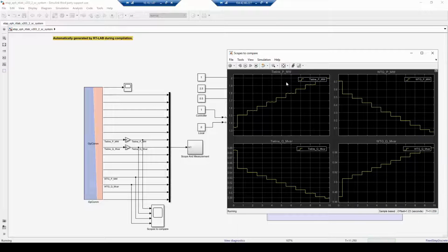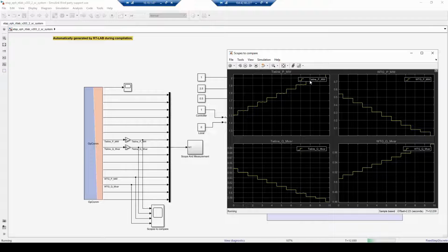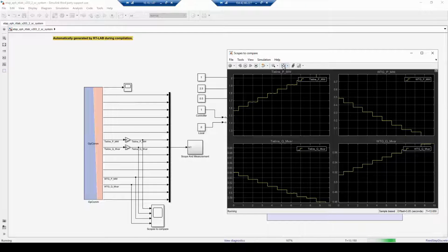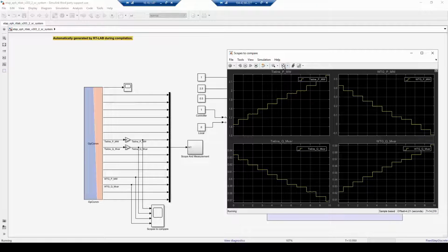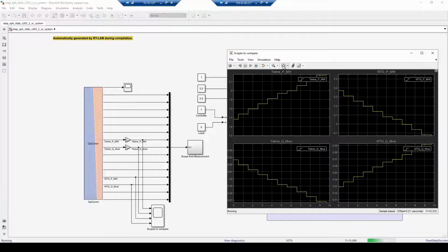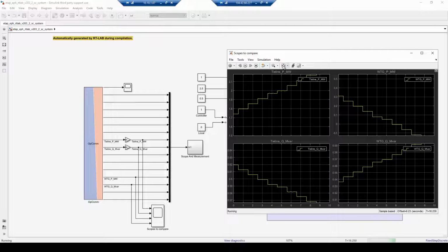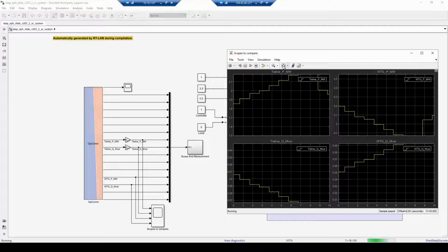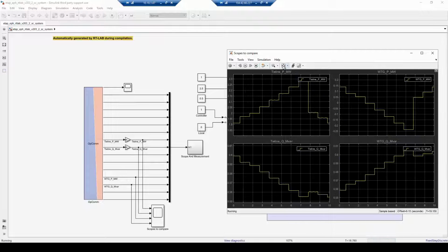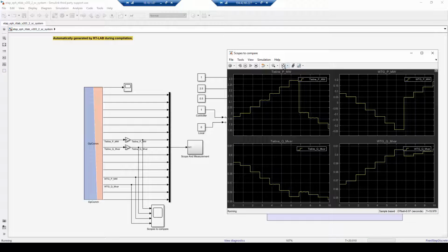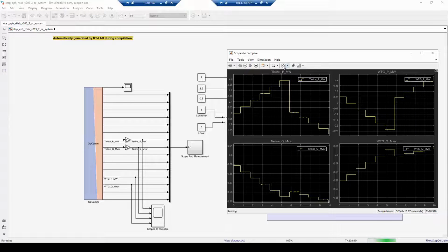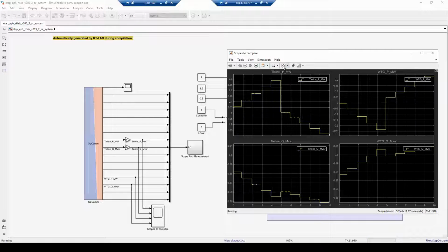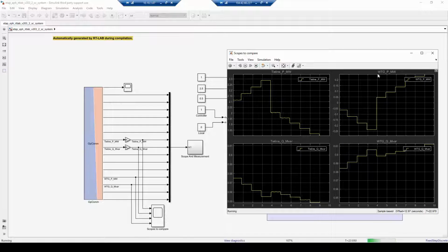As we can see, the tie line flow is around 2 megawatts. Now the controller will try to control the tie line flow to the set points which were defined in the ETAP control logic. Now it will compensate and make the tie line flow 1 megawatt and the reactive power 0.5 megavars, and that will be compensated with the help of the WTG.